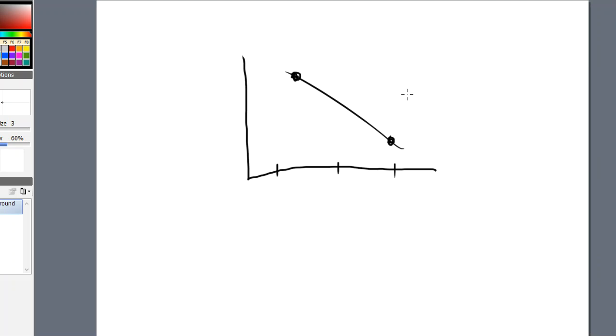And you are still assuming that those two solutions are completely perfect. There's no problems with them. They are fresh. They are made correctly. There's no kind of weird things that happen when you measure them, because you're measuring the millivolts that's getting generated from these buffers onto your pH probe. That's how those work. So with that said, we have to do better. We have to make sure that 2 points are really getting self-checked.